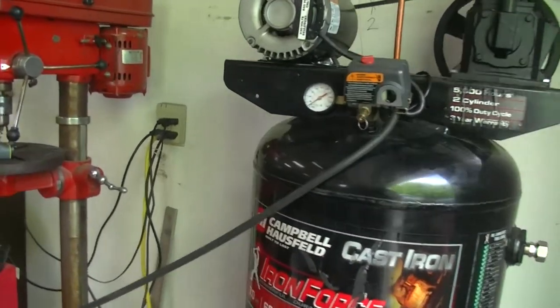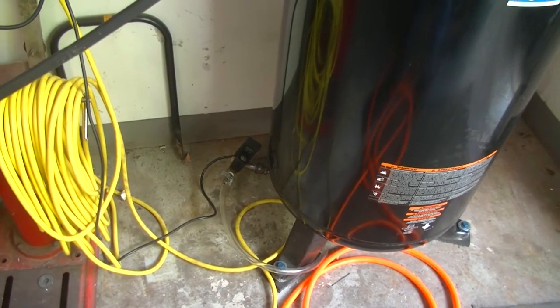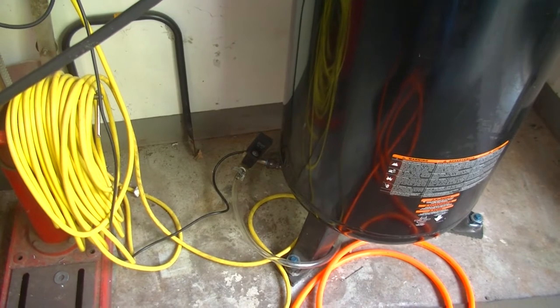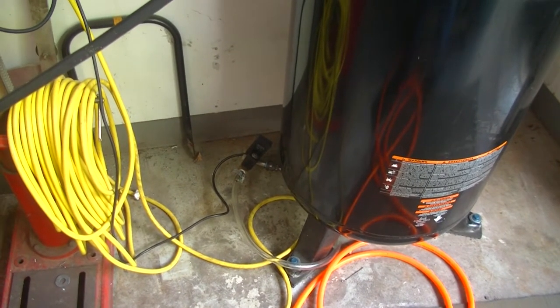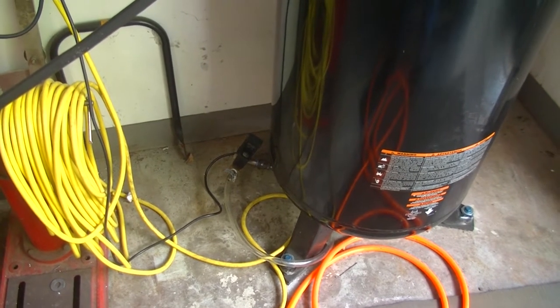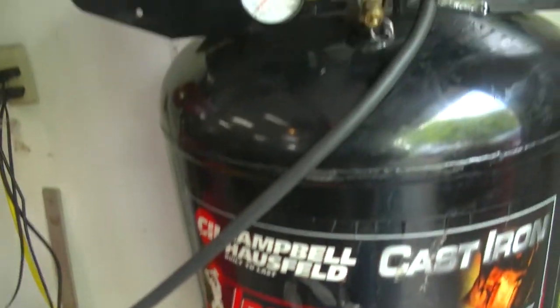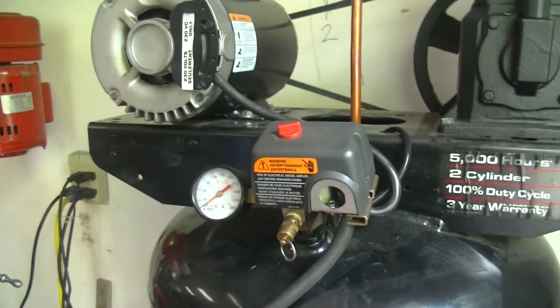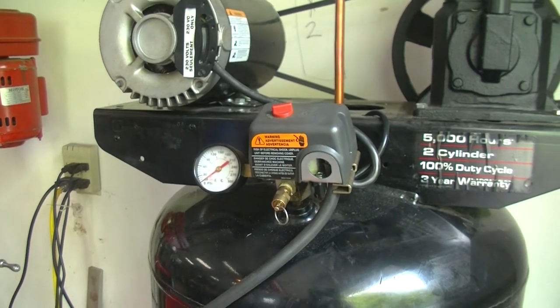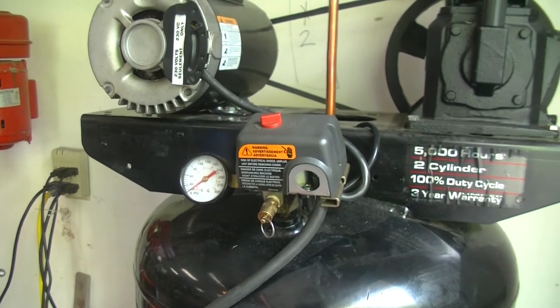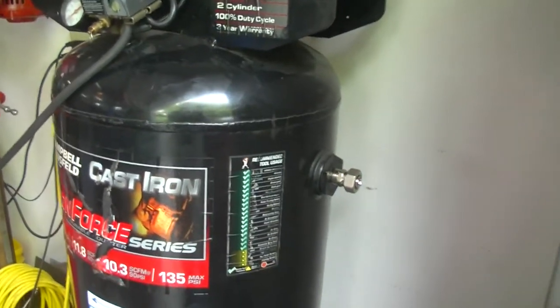Alright, we've done a couple of things since the last episode. I have taken that entire spitter valve assembly apart. It just bleeds off the moisture off the bottom of the tank. That is fixed now. I have taken apart and gone in and cleaned the pressure switch. And so now it shuts off at the appropriate time.